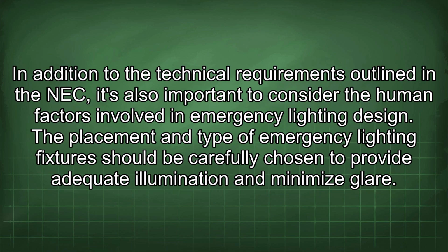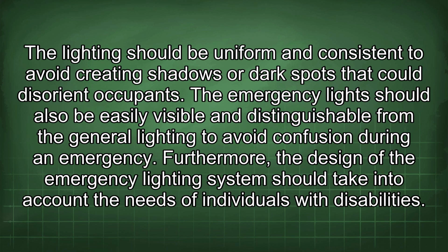In addition to the technical requirements outlined in the NEC, it's also important to consider the human factors involved in emergency lighting design. The placement and type of emergency lighting fixtures should be carefully chosen to provide adequate illumination and minimize glare. The lighting should be uniform and consistent to avoid creating shadows or dark spots that could disorient occupants. The emergency light should also be easily visible and distinguishable from the general lighting to avoid confusion during an emergency.